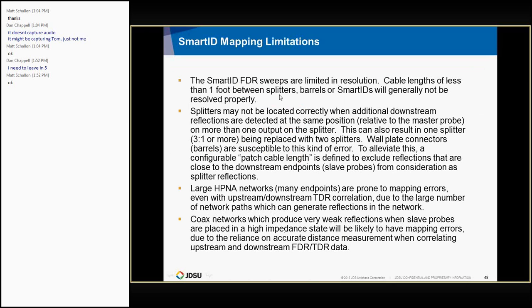Okay, Smartid mapping limitations. The Smartid FDR sweeps are limited in resolution. Cable lengths of less than a foot between splitters, barrels, and Smartids generally won't be picked up right. Splitters may not be located correctly when you have additional downstream reflections detected at the same position relative to the master. And it gets kind of complicated explaining this, but there is a configurable thing called a patch cable length that is basically a distance within which it won't try to combine, won't try to merge a common reflection point into a splitter.